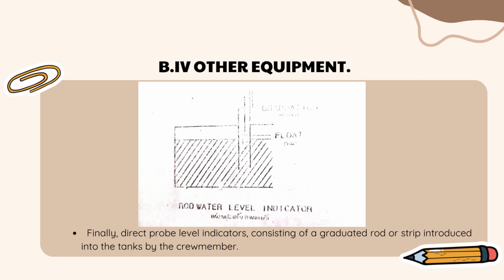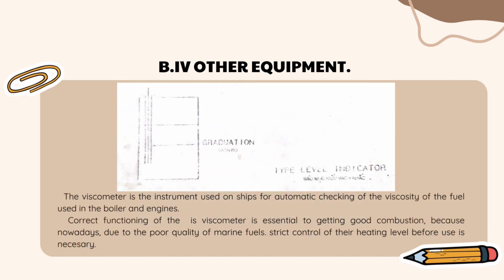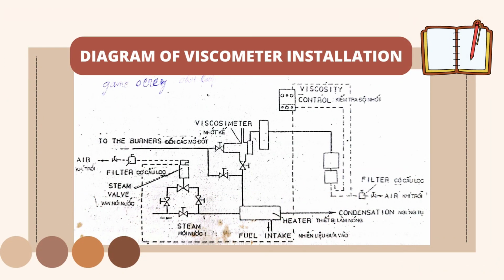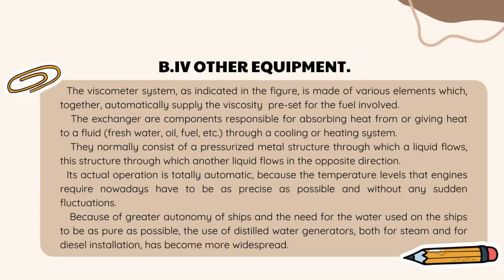by the crew member. The viscometer is the instrument used on ships for automatic checking of the viscosity of the fuel used in the boiler and engines. Correct functioning of the viscometer is essential to getting good combustion, because nowadays, due to the poor quality of marine fuels, strict control of their heating level before use is necessary. Diagram of viscometer installation. The viscometer system, as indicated in the figure, is made of various elements which, together, automatically supply the viscosity preset for the fuel involved.